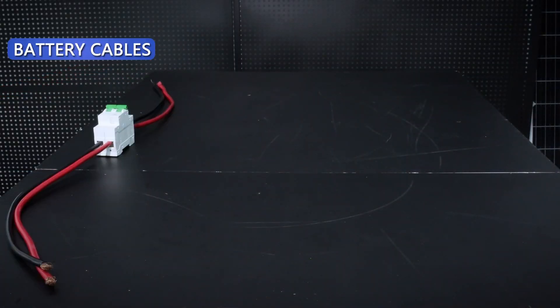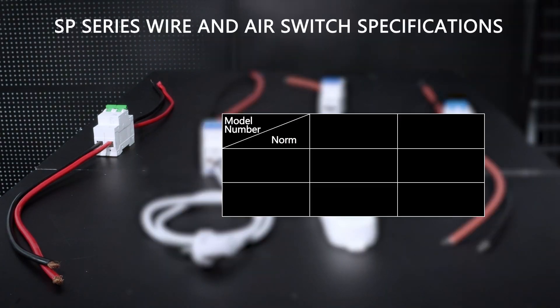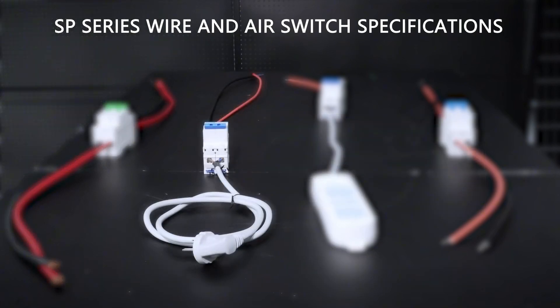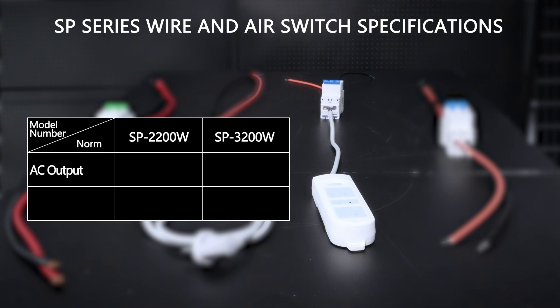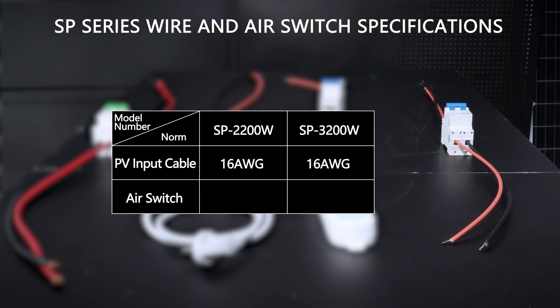Battery Cables, AC Input Cable, AC Output Cable, PV Input Cable. SP-2200W and SP-3200W require battery cable with 6 AWG and switch 250R and 200R respectively. AC Input Wire: 12 AWG, 10 AWG out, switch 20R and 32R respectively. AC Output Wire: 12 AWG, 10 AWG out, switch 20R and 32R respectively. PV Input Wire: 16 AWG, 16 AWG, switch 15R and 15R respectively.